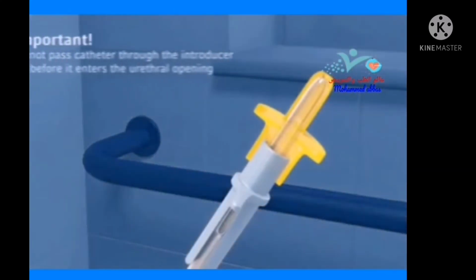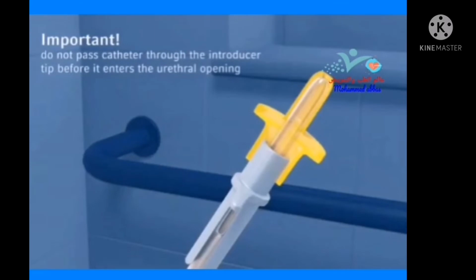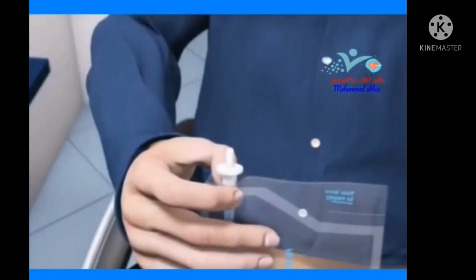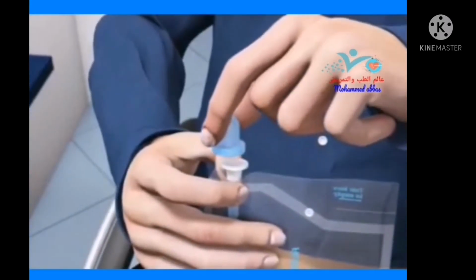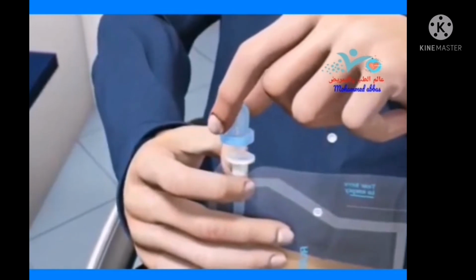The introducer tip is one of the main features of the MMG closed system for helping to reduce the risk of urinary tract infection. The introducer tip protects the catheter, allowing it to bypass the first 1.5 centimeters inside the urethra where the majority of the bacteria reside. Therefore, it is very important that the introducer tip is inserted into the urethra the full 1.5 centimeters before you start advancing the catheter. If needed, add some extra gel to the introducer tip. The gel can be found inside the protective cap.